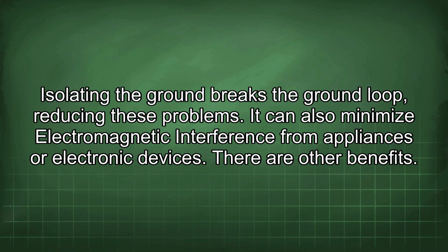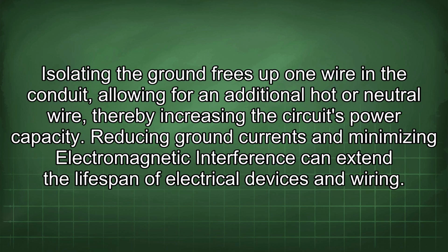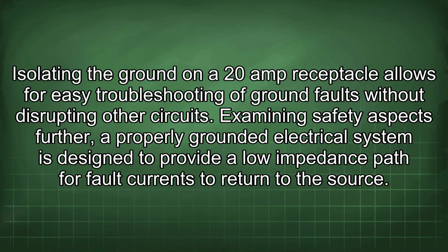There are other benefits. Isolating the ground frees up one wire in the conduit, allowing for an additional hot or neutral wire, thereby increasing the circuit's power capacity. Reducing ground currents and minimizing electromagnetic interference can extend the lifespan of electrical devices and wiring. Isolating the ground on a 20-amp receptacle allows for easy troubleshooting of ground faults without disrupting other circuits.